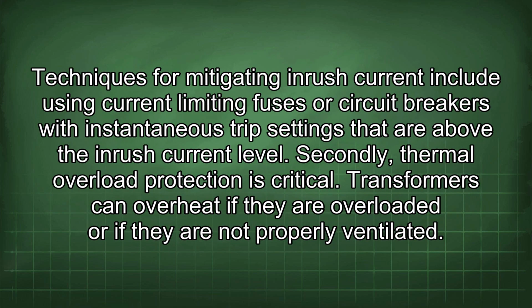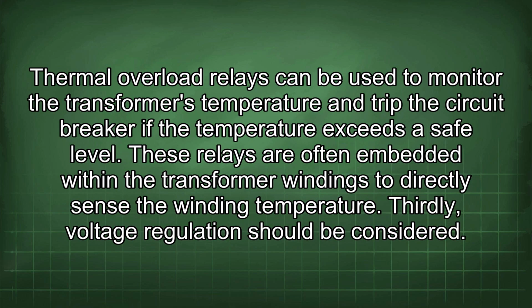Techniques for mitigating inrush current include using current-limiting fuses or circuit breakers with instantaneous trip settings that are above the inrush current level. Secondly, thermal overload protection is critical. Transformers can overheat if they are overloaded or if they are not properly ventilated. Thermal overload relays can be used to monitor the transformer's temperature and trip the circuit breaker if the temperature exceeds a safe level. These relays are often embedded within the transformer windings to directly sense the winding temperature.